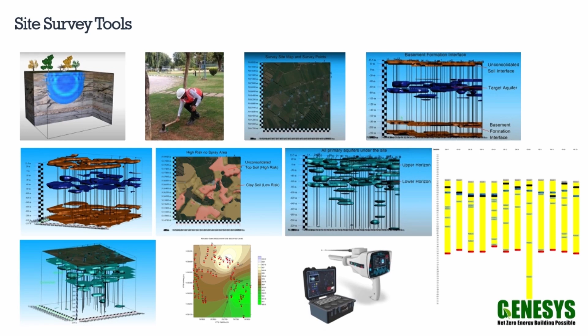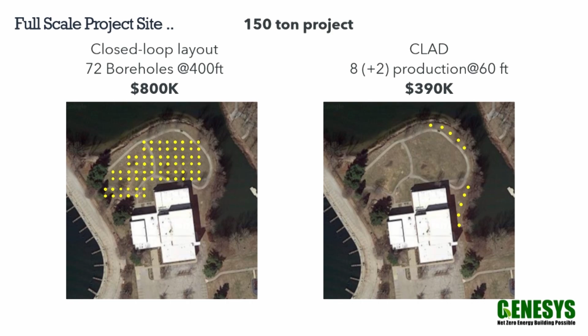An example of a current project we are wrapping up. The client wanted a typical closed loop design, so they got quotes for it, and this is them allowing us to share this information. It's a 150-ton project. The closed loop needed about 72 boreholes at 400 feet each, and the total cost of all the outside work was about $800,000. We were able to do all of that with 10 boreholes, basically 10 wells, at 60 feet deep, and the total cost was less than almost half.